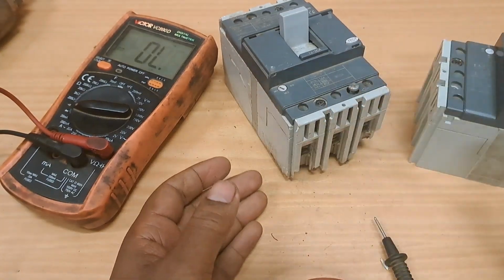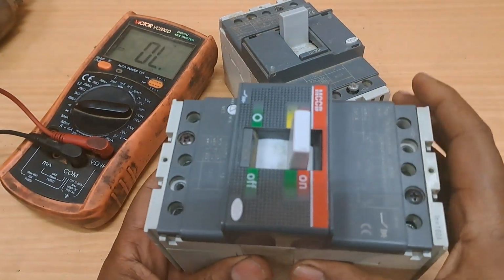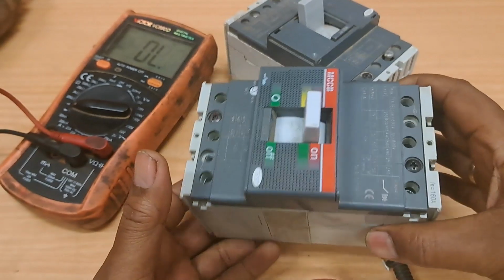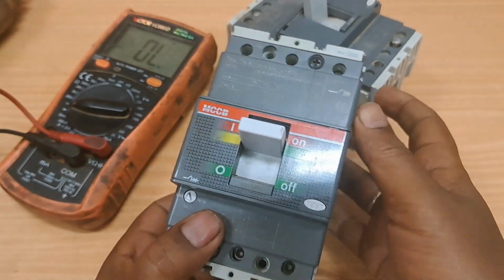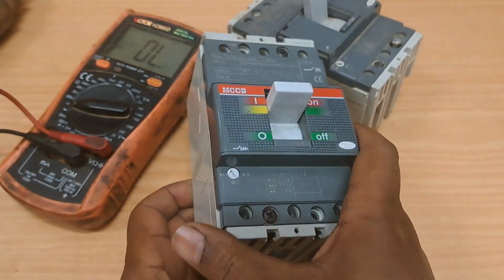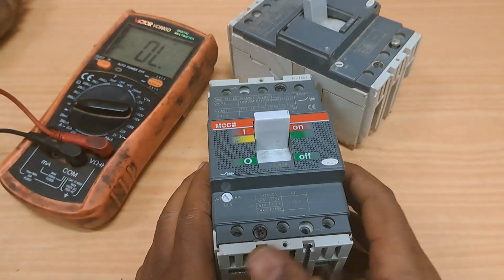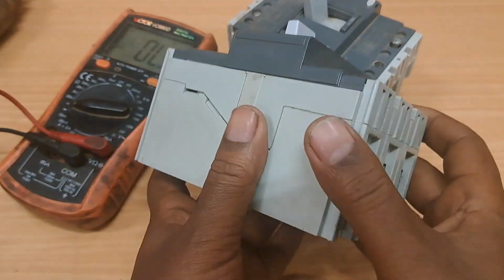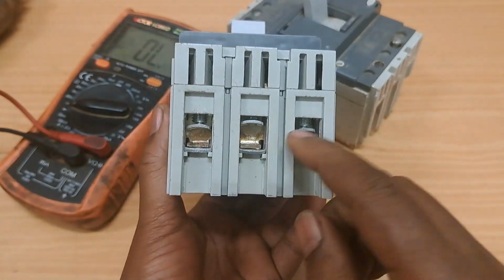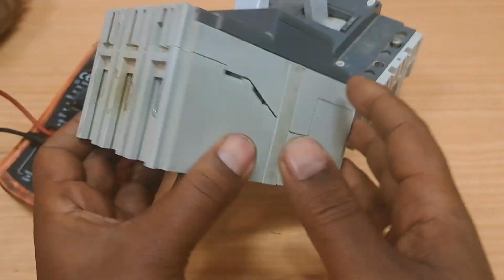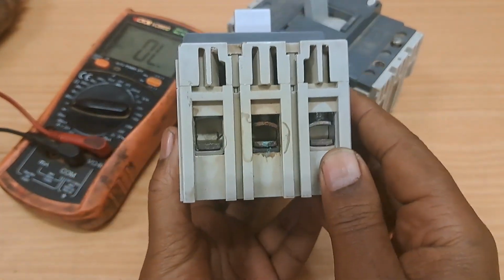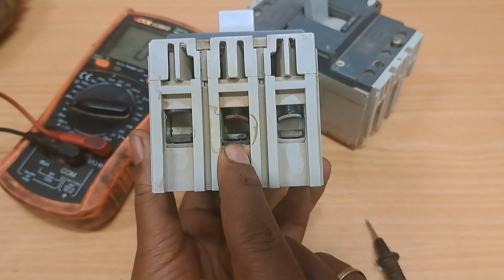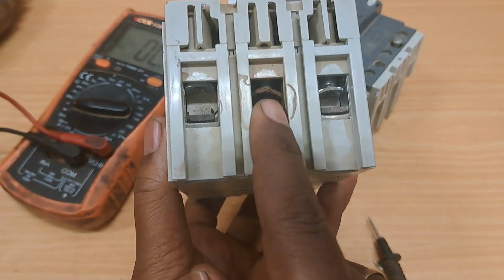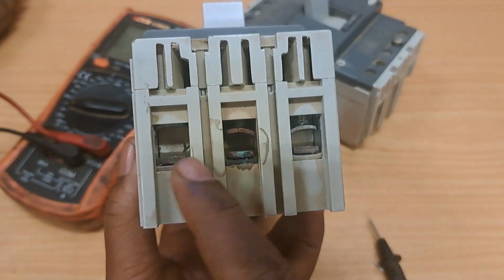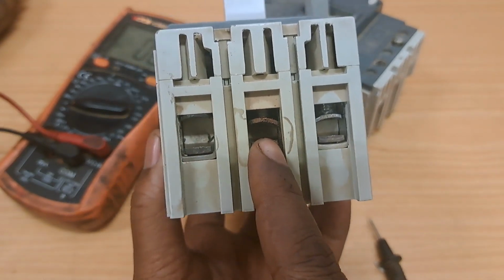Similarly, we have another breaker with 160 ampere. Let's go ahead and measure operation of this breaker. Physical inspection: when you look at it physically, there is no visible damage. But when you look right here, you see there is a burned contact. So more probably, this might be defective due to this excessive current.